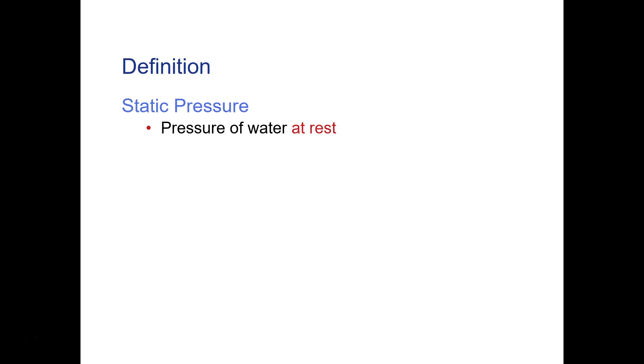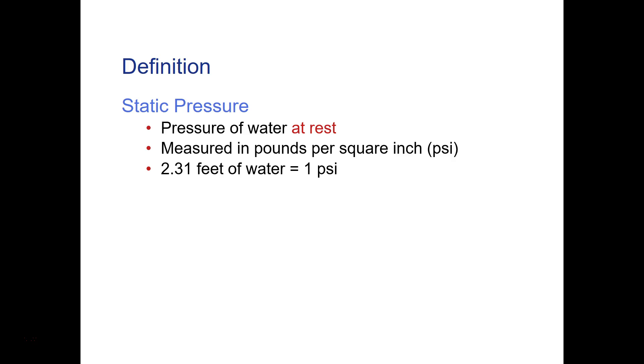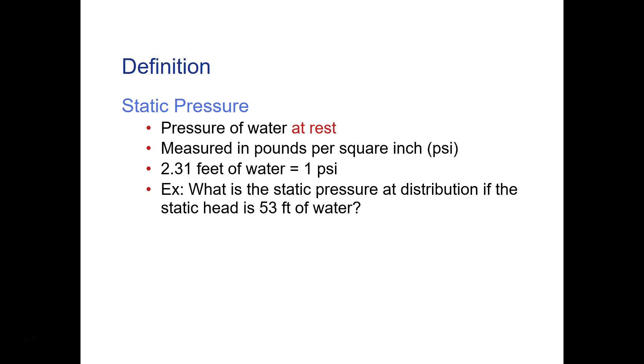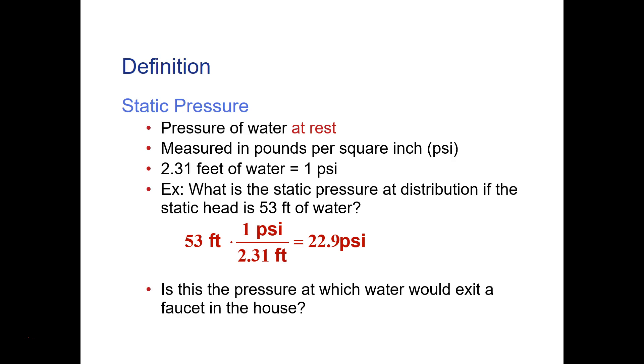Static pressure is the water pressure at rest, measured in PSI. Going back to the earlier relationship: for every 2.31 feet of water, that equals 1 PSI. So for that same 53 feet of static head, the static pressure equals 53 times (1 PSI / 2.31 feet), which gives 22.9 PSI. Is that enough water pressure for a house? No — that's not nearly enough.